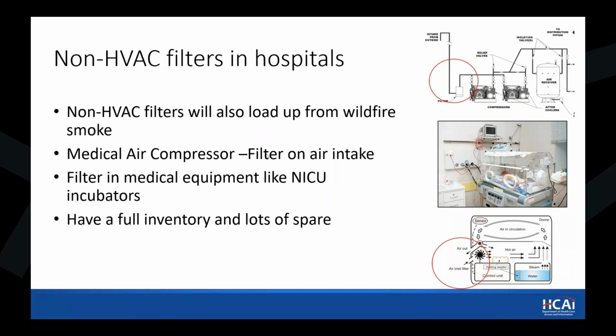I've also heard of a hospital that had issues in their NICU incubators. They realized that the NICU incubators, where you put the newborn babies, actually have HEPA filters, a special type of filter, in them. When there was wildfire smoke, those filters were loaded with wildfire smoke, even though the main system was filtering, but there were still some particles making their way there.